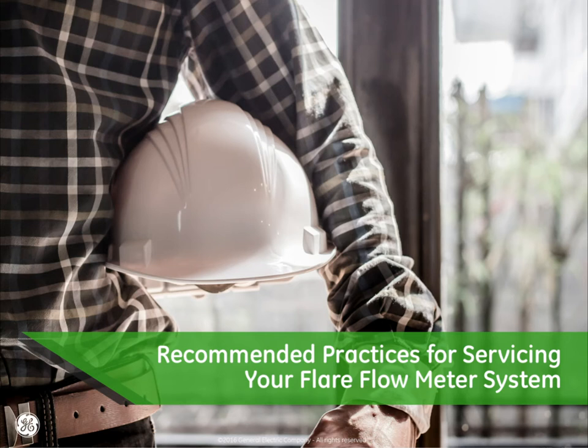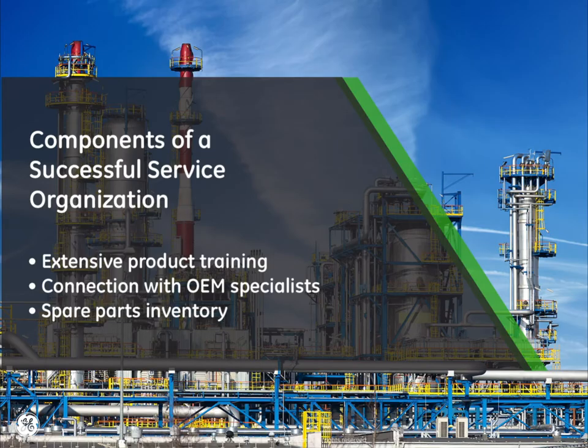I'd like to highlight a few best practices that are important for any service organization that works on flare applications. First, all field service representatives, whom I'll hereon refer to as FSRs, should undergo extensive product training. Flare lines present a dangerous environment and require a high degree of specialization. Therefore, I feel that training is necessary to ensure that meters are both correctly installed and properly serviced. As a quick example, GE holds mandatory quarterly stand-downs for FSRs to provide technical updates and revisit safety precautions. This ensures that our technicians aren't getting careless as they become more and more comfortable with the job. Your provider of choice should also stay in frequent contact with the OEM product development teams. This helps to verify that FSRs are up to date on the latest technological advances and any new servicing methods. Lastly, spare parts replacement may be required in order to resolve any operational issues that may arise in the field. Therefore, it's important for technicians to maintain an inventory of spare parts. At GE, we refer to this inventory as trunk stock, which is made available for any on-site field visit.